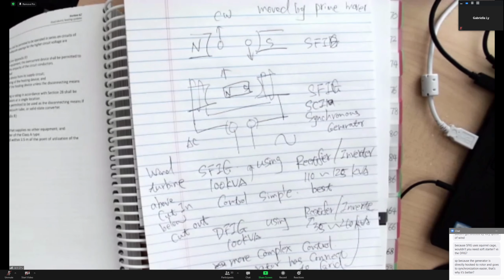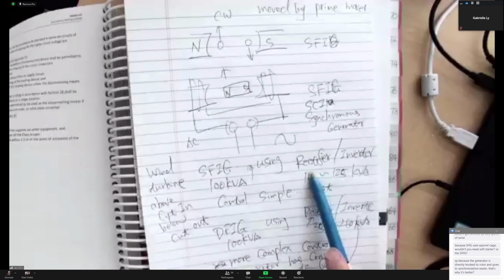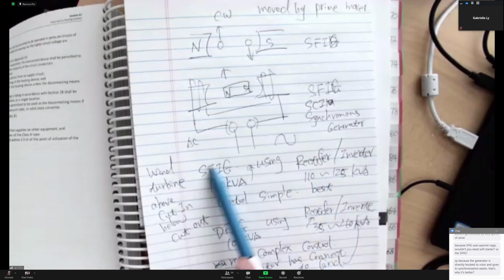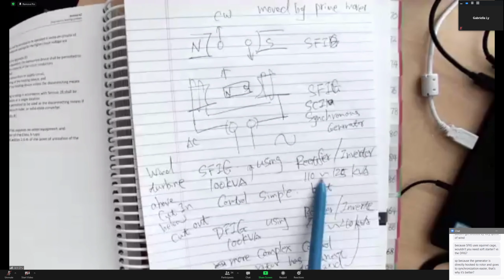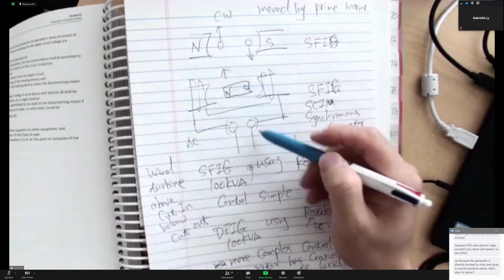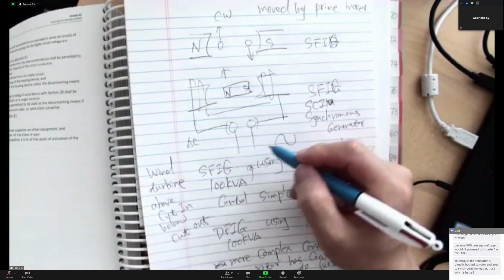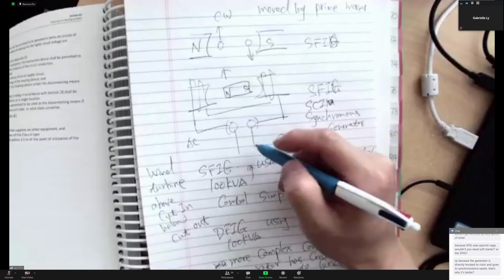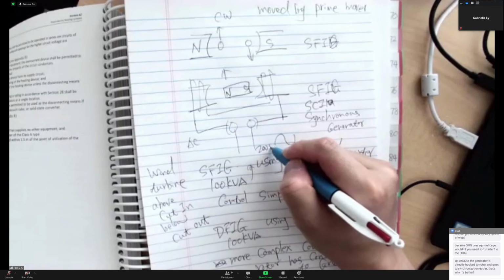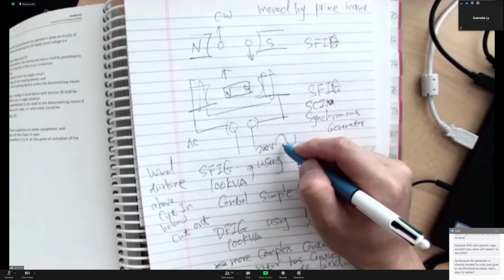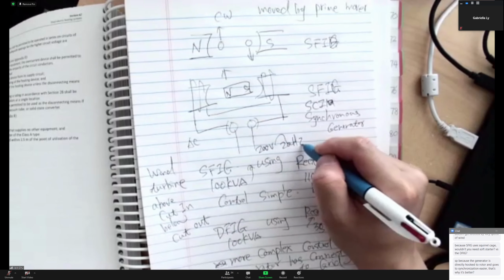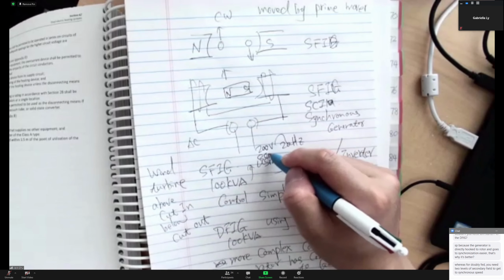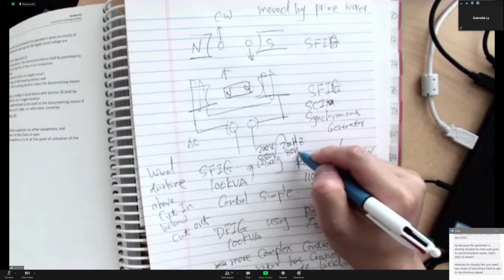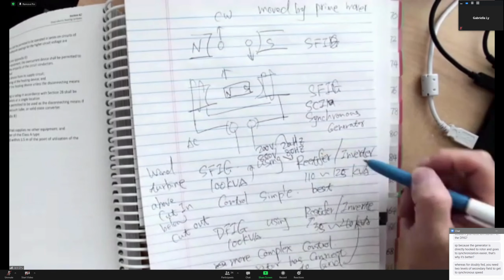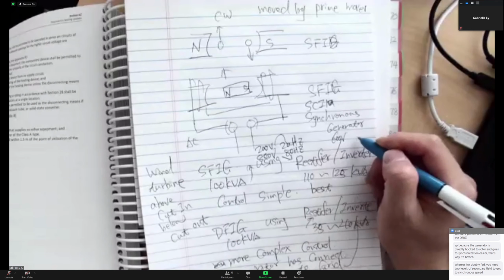Yeah. It's because when you put this in there, it doesn't matter how the wind speed changes, whether from the rotor part or from the stator part, you can have anything. Let's say you will generate between 200 volts and maybe 20 hertz, all the way to 800 volts, 80 hertz. You feed into this combination, you always come out 600 volts, 60 hertz.